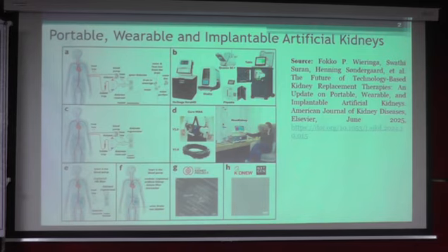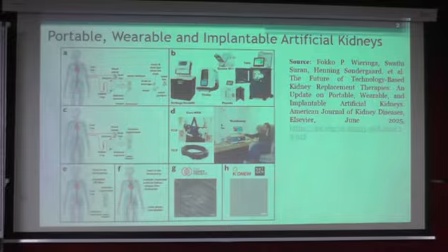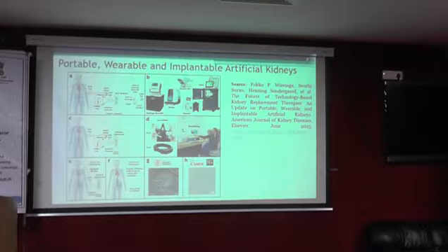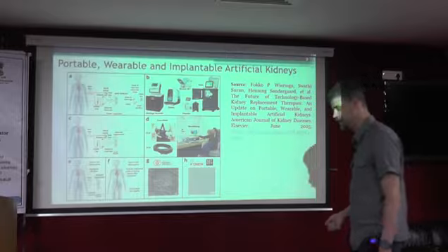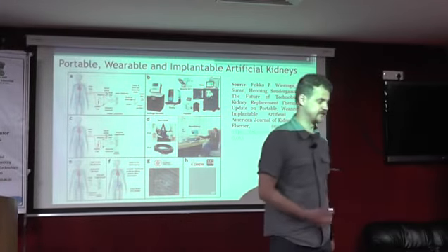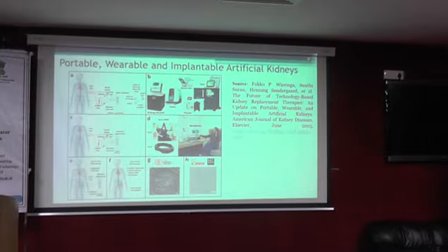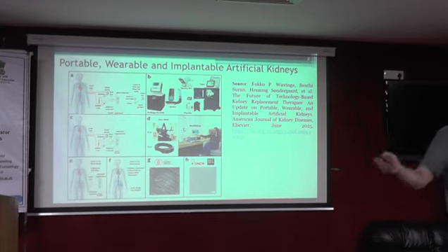Yeah, the primal concern, if we talk about hemodialysis, is actually the water supply. In order to perform a hemodialysis procedure, if we talk about conventional dialysis methods, it usually goes for 120 to 150 liters per patient. At the same time, the production of this volume of dialysis fluid requires an even bigger amount of water that has to be specifically prepared for the dialysis for medical purposes.